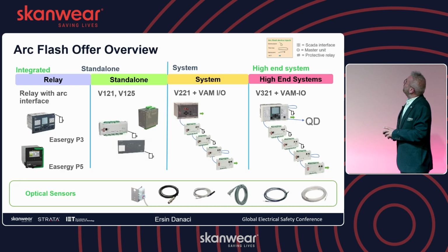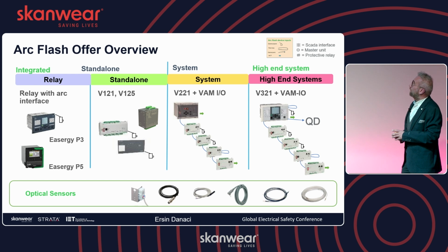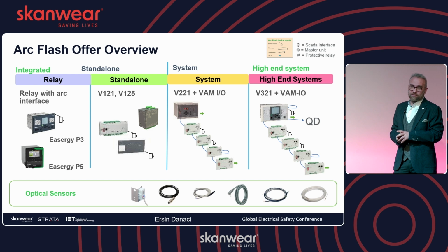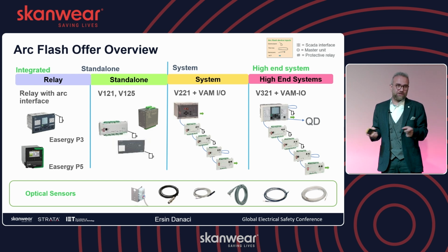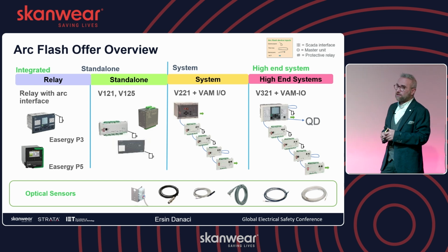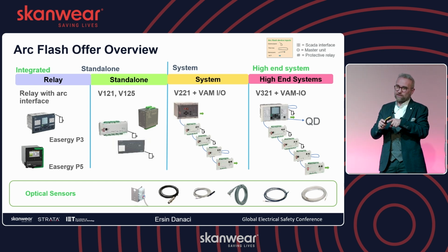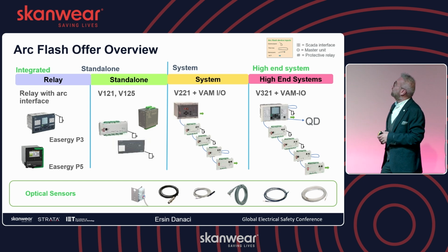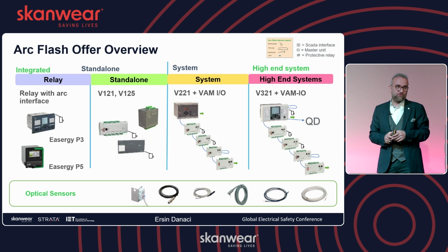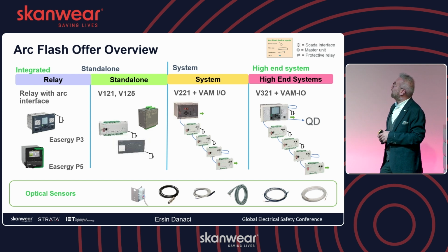From the technology point of view, for the MV switchgear, we can use standalone protections. But if we have multiple substations in different locations, then we will need coordination, and in that case we may need to utilize a central intelligent device that can communicate with the extension modules. This requires communication between the central unit and extension modules. In each extension module, we can install up to 10 sensors, and on the central unit we can install another 10 sensors. So considering the number of sensors, we can decide the number of extension modules.